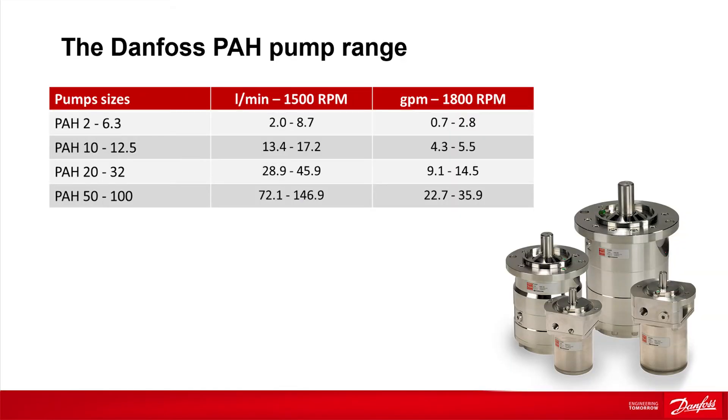We offer a pump range from 2 liters per minute to 147 liters per minute at 1,500 RPM. For larger flows, Danfoss recommends to place more pumps in parallel. This is not only simple, it also increases the uptime.